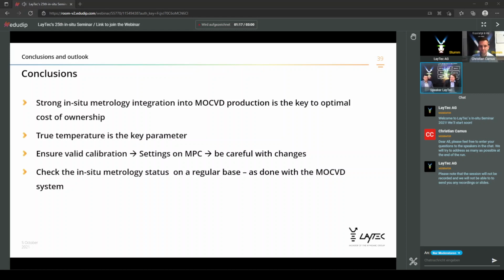So the bottom line is always ensure a valid calibration, ensure a correct setting in the entire system, also on the MPC itself, including low-level configuration settings as well as run type or wafer table setup. Be careful with any changes on the system in order not to destroy the entire system calibration or consistency. Always check the in-situ metrology status on a regular basis. Put it in your regular scheduled maintenance period along with the MOCVD system. It's important to maintain both the metrology system as well as the entire MOCVD system in terms of cleaning viewports, wafer positioning and so on, in order to maintain the consistency of the entire system.